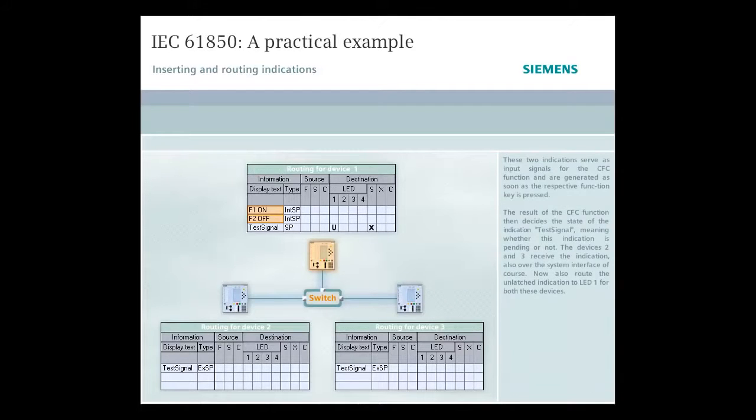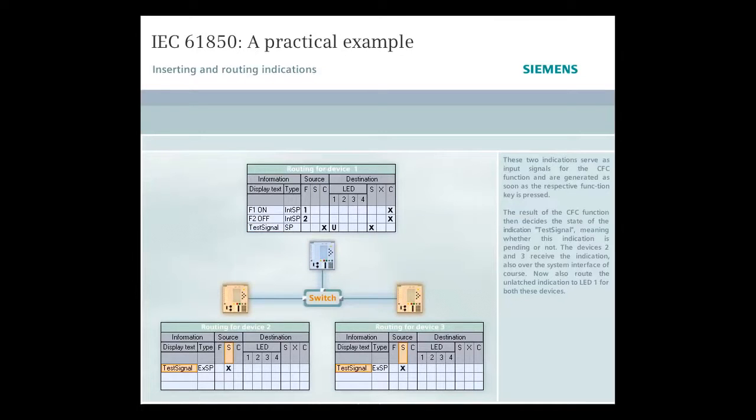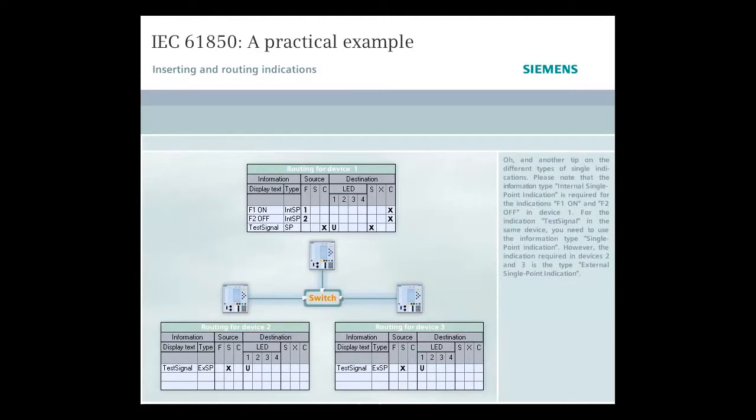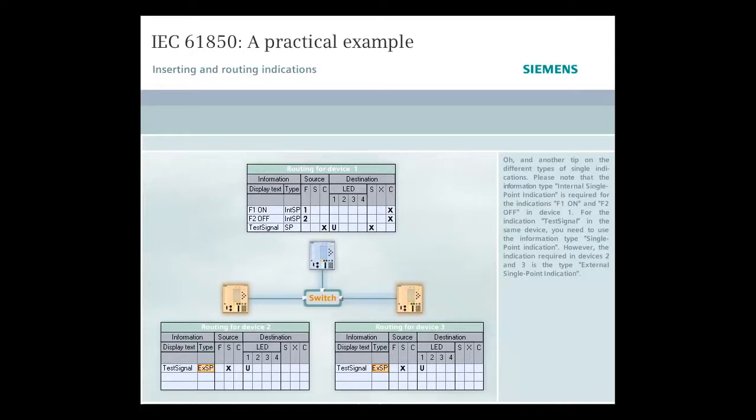These two indications serve as input signals for the CFC function and are generated as soon as the respective function key is pressed. The result of the CFC function then decides the state of the indication test signal, meaning whether this indication is pending or not. The devices 2 and 3 receive the indication, also over the system interface of course. Now, also route the unlatched indication to LED1 for both these devices. And another tip on the different types of single indications. Please note that the information type internal single point indication is required for the indications F1 On and F2 Off in device 1. For the indication test signal in the same device, you need to use the information type single point indication. However, the indication required in devices 2 and 3 is the type external single point indication.